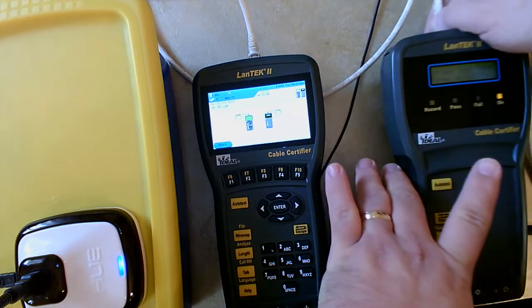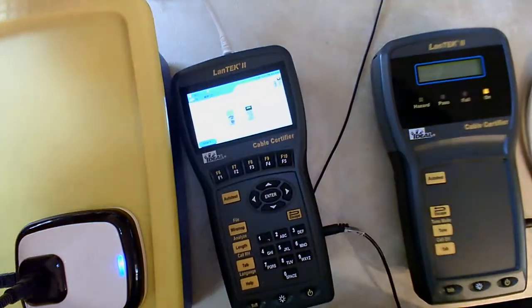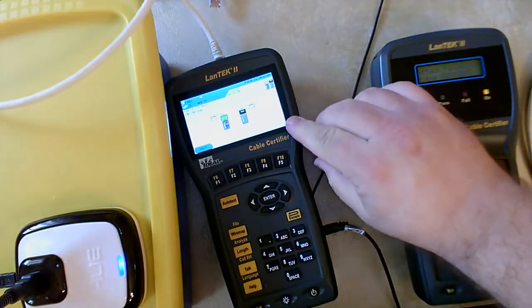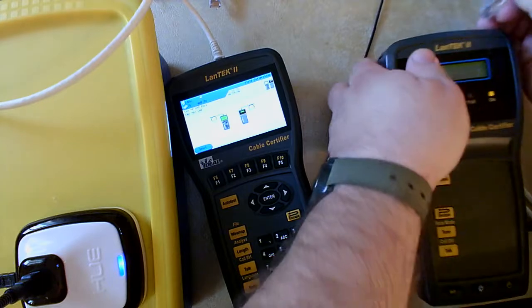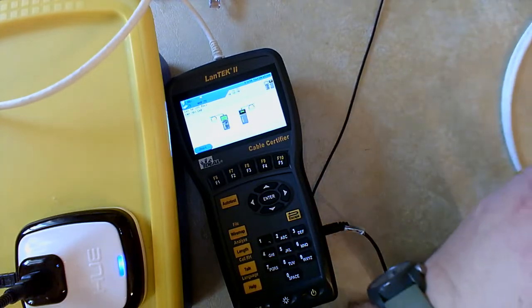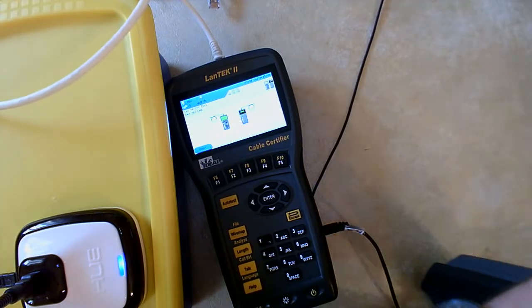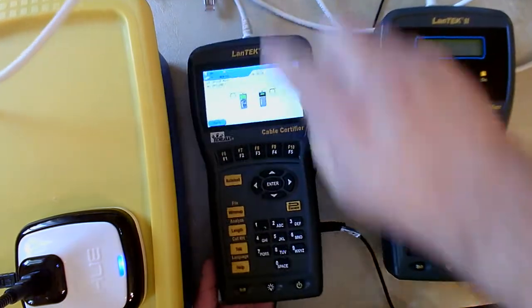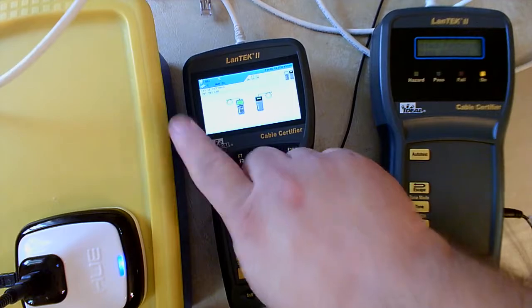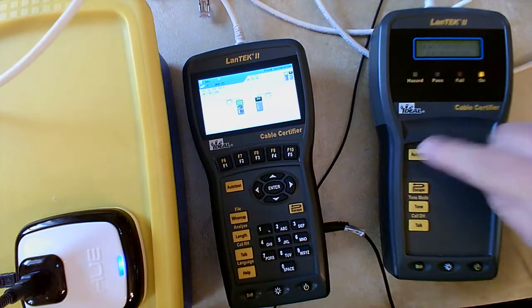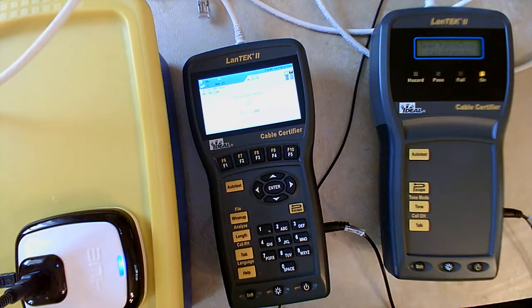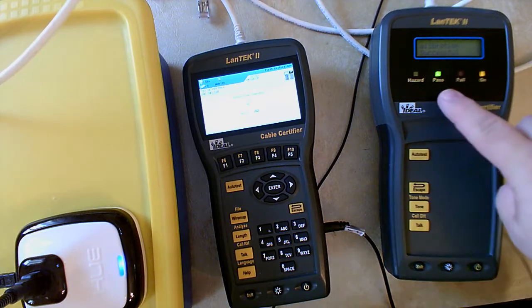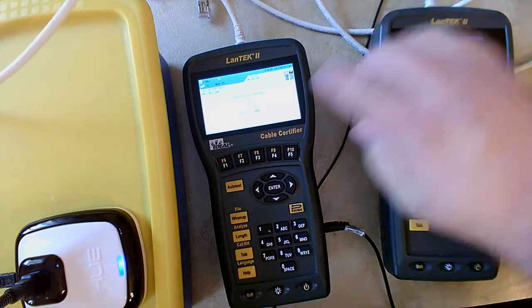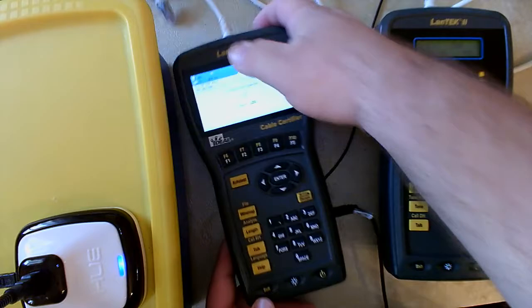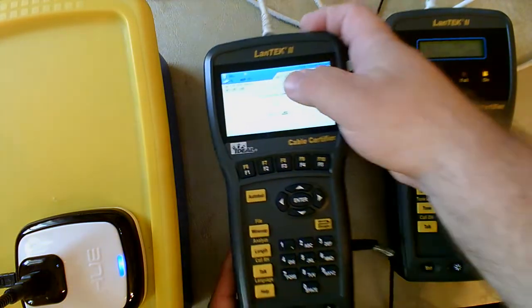Now it wants me to leave the left-hand cable in place over here, and take the right-hand cable I had used previously, plug it into this side, and leave it in place. It's going to want me to hit start over here to finish calibration on this cable, and hit auto test over here to finish calibration on this one. Once it's done, I'll see a pass over here that it's okay with this cable, and a little pass check mark over here that's okay with this cable.